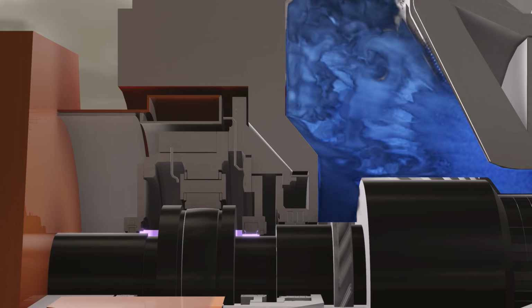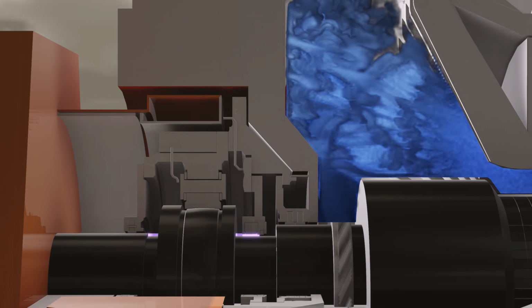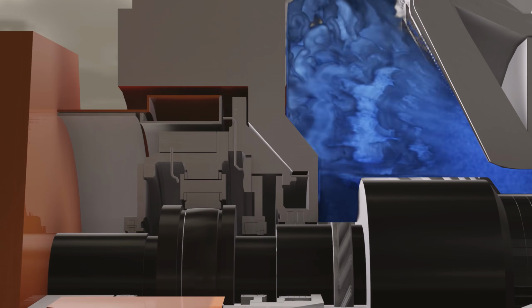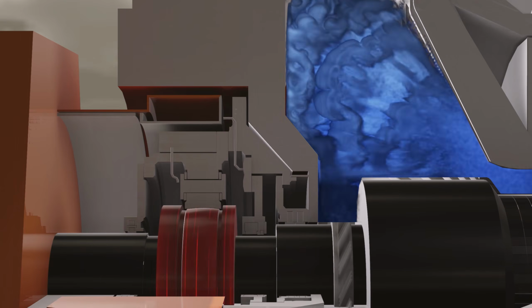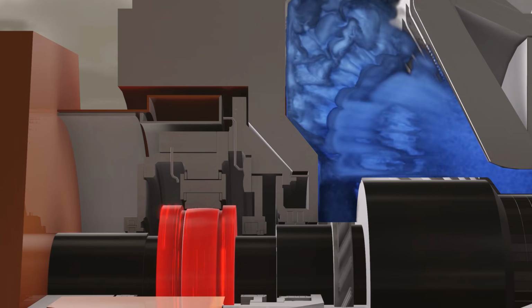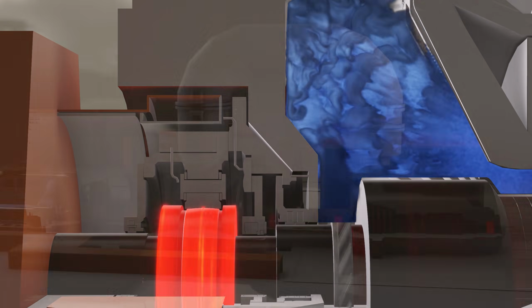Without AC power, the bearing lubrication oil pumps and hydrogen seal oil pumps stop working. And without DC power, the emergency DC pumps don't work either.